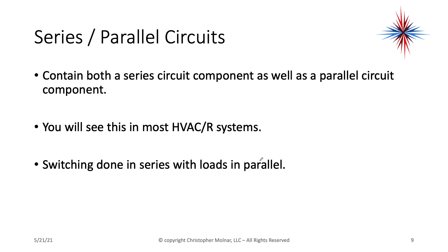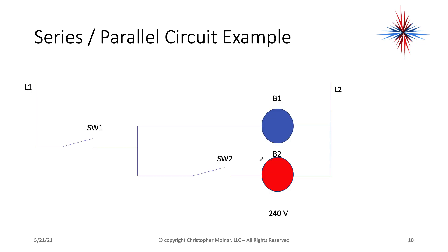We have a third type of circuit that contains both a series component and a parallel component — you see this in most HVAC systems. Switching is done in series with loads in parallel. In this example of a series-parallel circuit, switch one controls current to both the top and bottom branches. If I close switch one, bulb one is operational. Switch two is still open so bulb two is not operational. If I close switch two, both bulbs are operational.